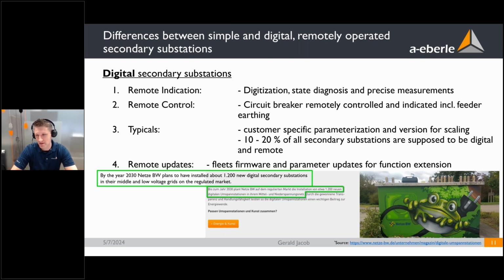Nobody has the time to go to 5,000 secondary substations and do firmware updates on 18,000 earth fault indicators if you want to change something. So you need to have a concept to do fleet updates regarding firmware, regarding parameters, regarding function extensions. And this is taken into account in the Netze BW concept. So as you can see below, Netze BW plans to have installed 1,200 digital secondary substations until 2030, so within the next 6 years.